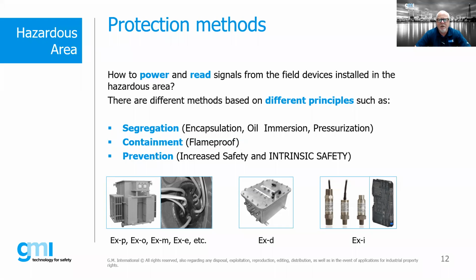There's what is called segregation, where we segregate the flammable mixture from the source of ignition. That could be encapsulation, oil immersion, or pressurization, so we're removing the flammable gas from that triangle. Containment is where we assume we're going to have a flammable air mixture come into contact with an ignition source, but it will be contained on the inside of, for example, a flameproof enclosure. That enclosure will not rupture, and it allows the hot flaming gas to escape through a flame path and cool off to an extent where it will not ignite the gas surrounding the enclosure.